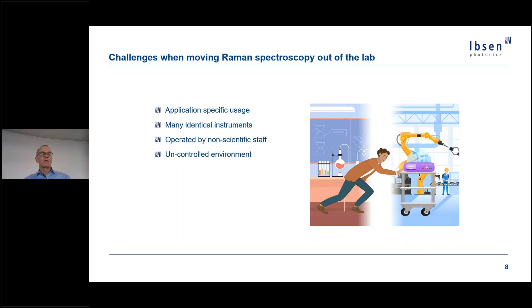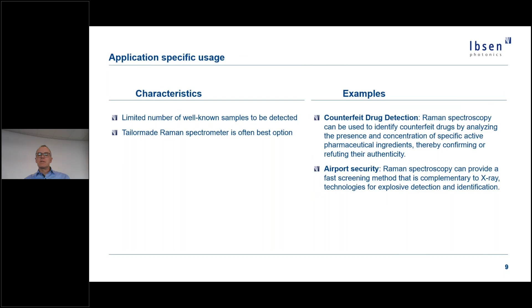As mentioned, industrial settings normally only require the instrument to detect a limited set of samples. This slide gives two examples of such applications. The first one is counterfeit drug detection, where the Raman spectrometer basically only needs to detect whether the active ingredient is present at the right quantity in a pharmaceutical tablet. Also, in airport security, Raman can be used to screen for a range of explosive materials. In these cases, a general purpose instrument will be overkill and too expensive. Instead, it's beneficial to have a spectrometer designed to fit the exact needs of the specific application.